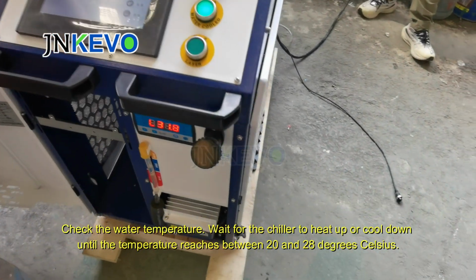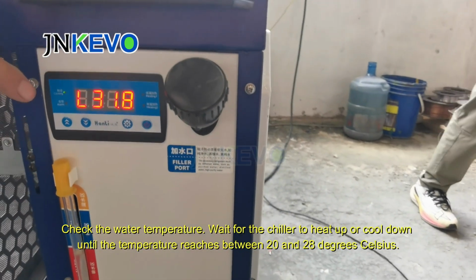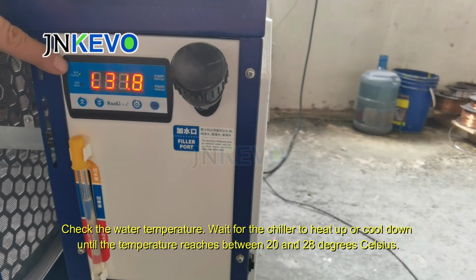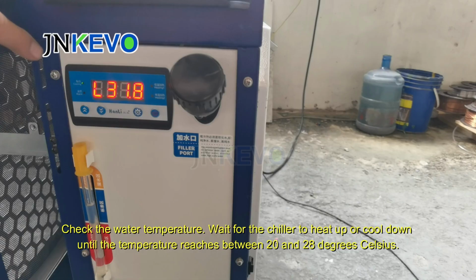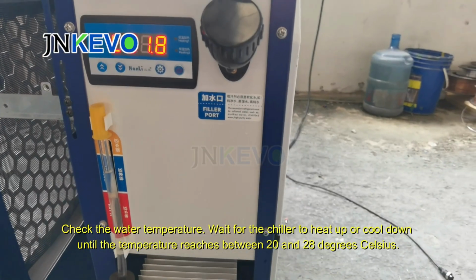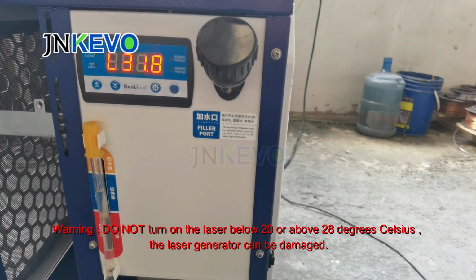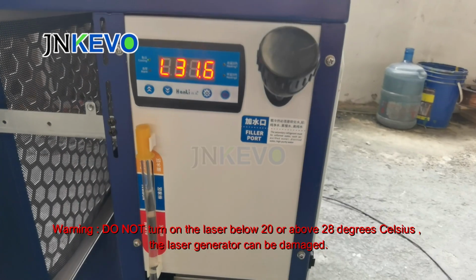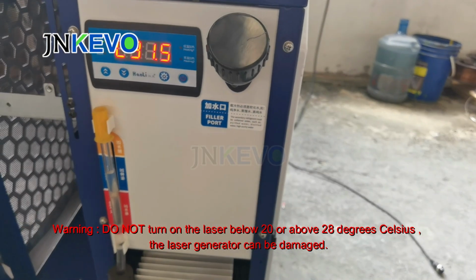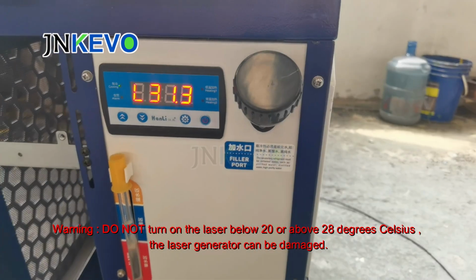Check the water temperature. Wait for the chiller to heat up, or cool down until the temperature reaches between 20 and 28 degrees Celsius. Warning: do not turn on the laser below 20 or above 28 degrees Celsius. The laser generator can be damaged.